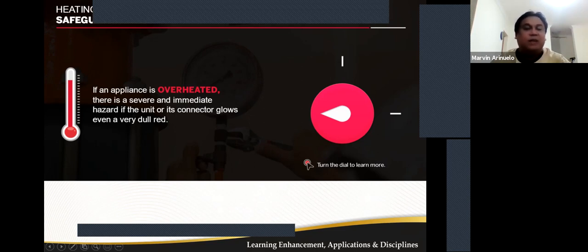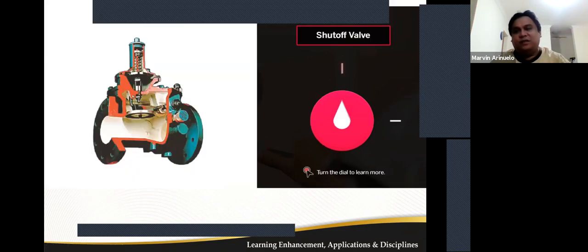Shut-off valves or safety shut-off valves prevent abnormal discharge of fuel. They should be constructed so they cannot be readily restrained or blocked in an open position. Such valves should close automatically when de-energized.